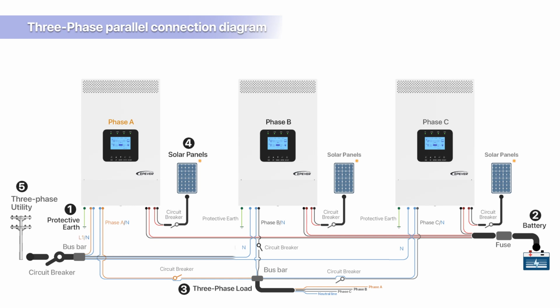The live wire should be connected separately in an A, B, C phase manner, ensuring that the grid power A, B, C phase aligns with the device's configured A, B, C phase. The wire gauge and length for the grid power input connection lines to each inverter should be uniform.